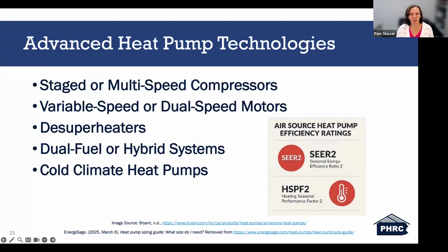Variable speed or dual speed motors. A lot of newer models of heat pumps and furnace blowers are equipped with electrically commutated motors, or ECMs, or variable speed or dual speed motors on their indoor fans, outdoor fans, or both even. These variable speed controls for the fans keep the air moving at a more comfortable velocity. They're minimizing cool drafts. They help maximize electrical savings, and they help reduce noise and disruption as well.